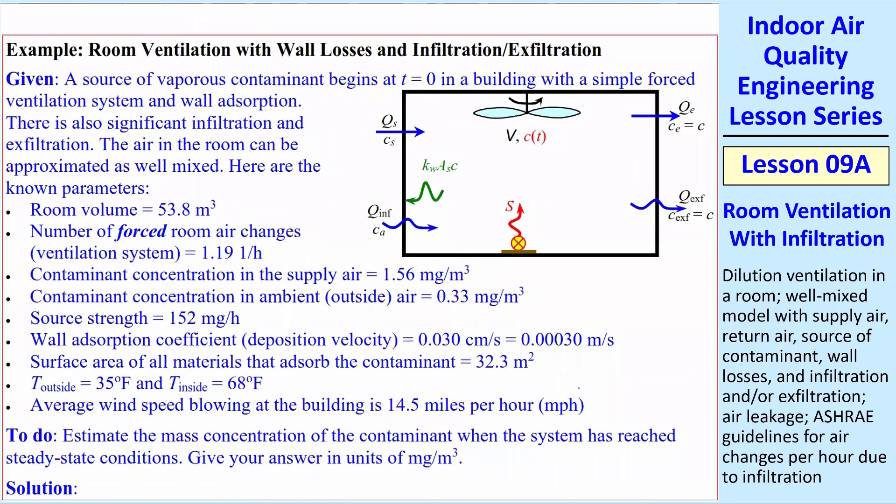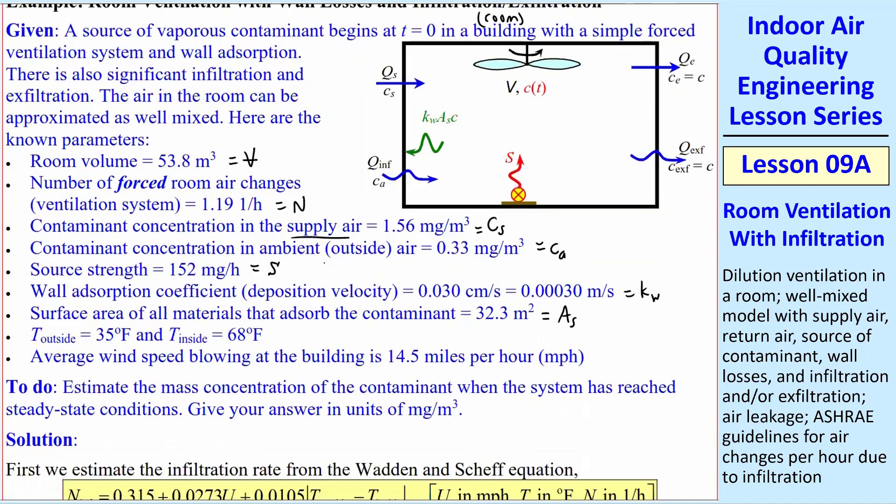So let's do one example. Very similar to a previous example we had, except now I've added infiltration and exfiltration. We have our parameters. So let's just identify these: room volume, V; number of forced room air changes, this is what we just call N through the ventilation system; the contaminant concentration in the supply air; outside ambient air; the source strength; the wall adsorption coefficient; the surface area of materials that adsorb; T outside and T inside; and the average wind speed is U in miles per hour.